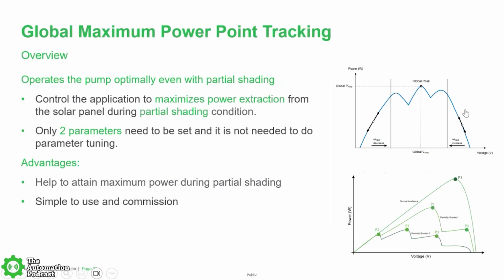The other feature that we have here is the global maximum power point tracking. This one we do need to enter two parameters, but this is really to automate different clouding seasons and times, to make sure that even when shading or less sun occurs on the next day versus the previous, there's an internal algorithm there that's going to make sure that our output power is going to maintain at the max of that shaded curve range.